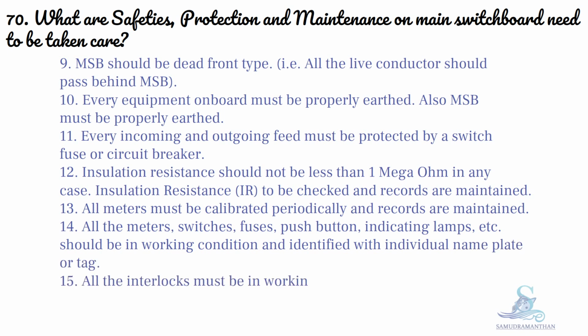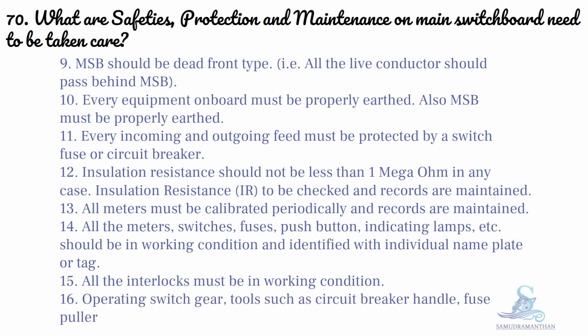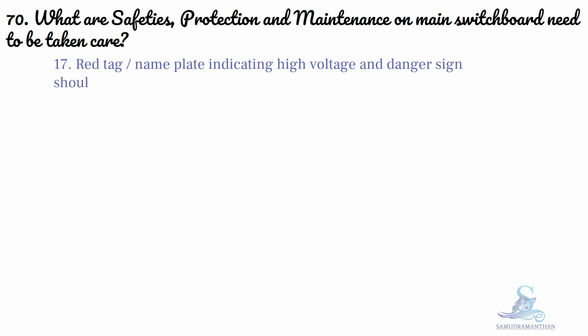All the interlocks must be in working condition. Operating switchgear tools such as circuit breaker handle, fuse puller, lamp grip, etc. must be readily available and to be used. A red tag or nameplate indicating high voltage and a danger sign should be fitted.